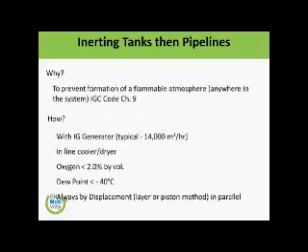How do we do it? Typically with an IG generator, normally on this size of vessel which you are working on, it is about 14,000 cubic meters. You can do it in a line cooler or dryer. Oxygen, ideally we should have the lowest possible, but it should be at least below 2%. Dew point temperature, we have discussed earlier, should be minus 40 degrees.